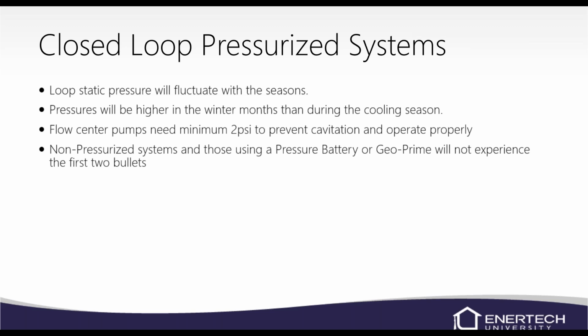If you have that issue, there are ways to fix it. We can use a pressure battery or a Geo-Prime tank, and we'll discuss those here in a few more minutes. But basically, then you don't have to worry about fluctuation of pressures in between the seasons. Again, those flow centers, the pumps need 2 psi to prevent cavitation. I know a lot of times we go out to job sites and we're always touching lines and feeling temperatures and things. If you ever walk up to a flow center pump and it's super hot, more than likely that's due to air. It's either air or there's debris and the pump's not getting cooled by the water that's in the system. So just keep that in mind.